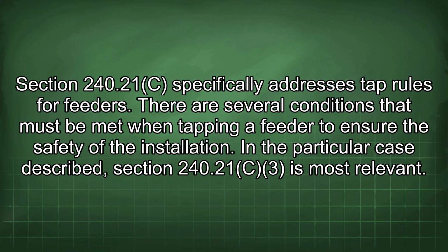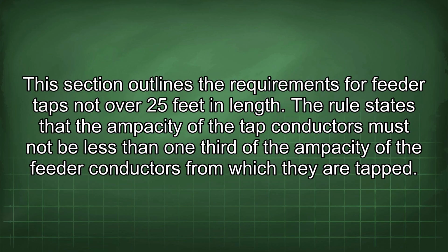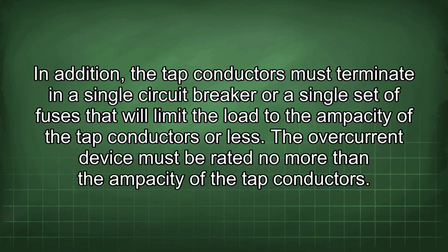In the particular case described, Section 240.21(C)(3) is most relevant. This section outlines the requirements for feeder taps not over 25 feet in length. The rule states that the ampacity of the tap conductors must not be less than 1/3 of the ampacity of the feeder conductors from which they are tapped. In addition, the tap conductors must terminate in a single circuit breaker or a single set of fuses that will limit the load to the ampacity of the tap conductors or less. The overcurrent device must be rated no more than the ampacity of the tap conductors.